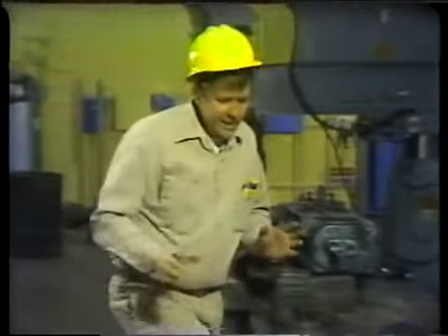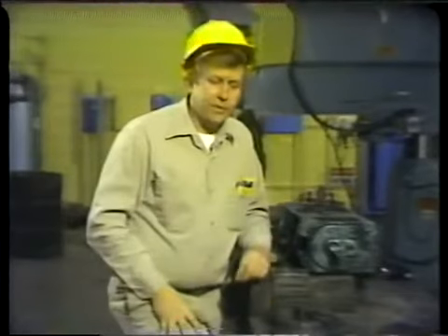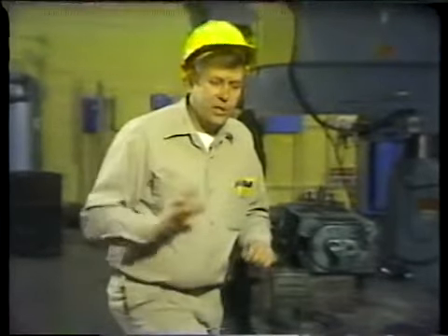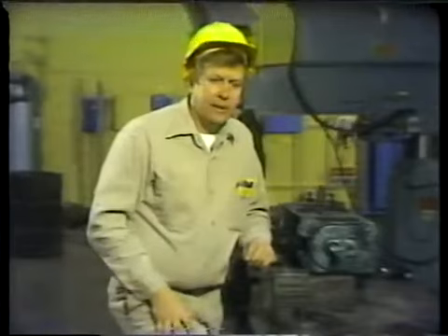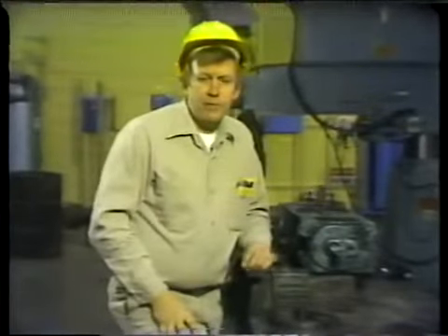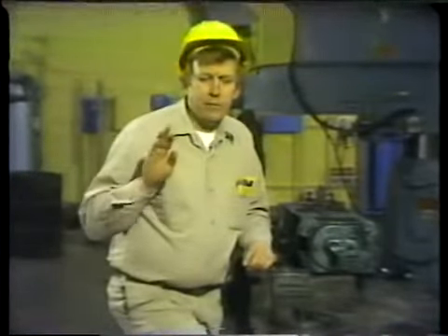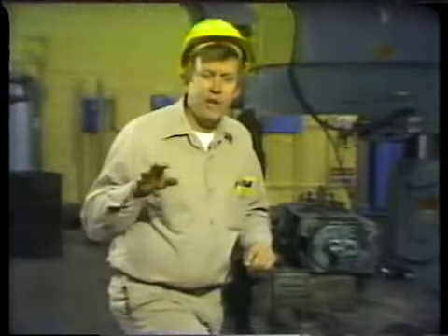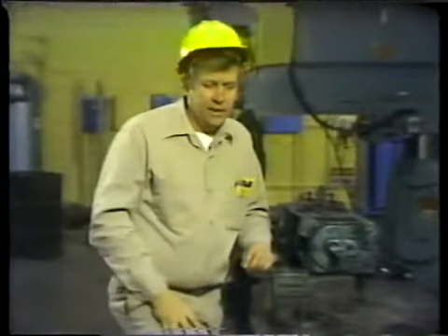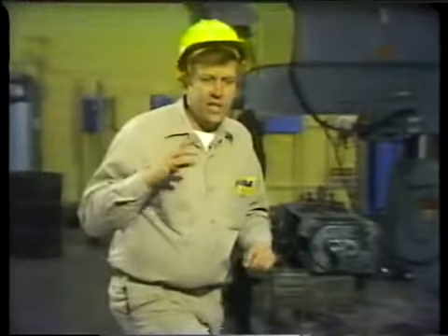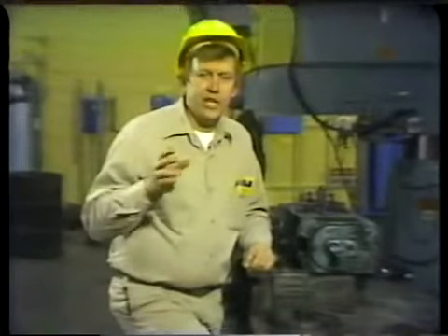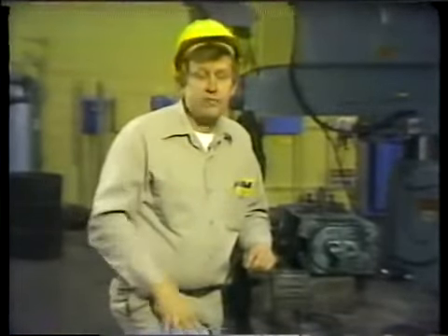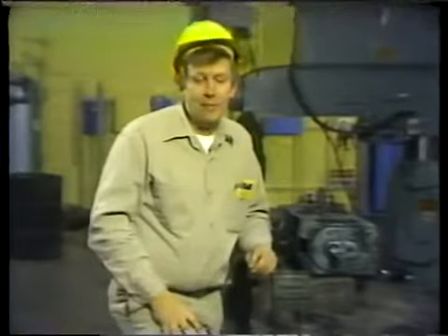So we had got everything ready so that we could go right inside and check it out and then get back out. If there was any problem, make the repairs. So my supervisor was there, and we were all waiting for the work permit. We come to find out, I found out at a later date, this fan had two circuits on it. It was an automatic circuit and a manual circuit. So evidently when they tagged it, they tagged the manual circuit and didn't tag the automatic circuit. At least this is what we think happened.